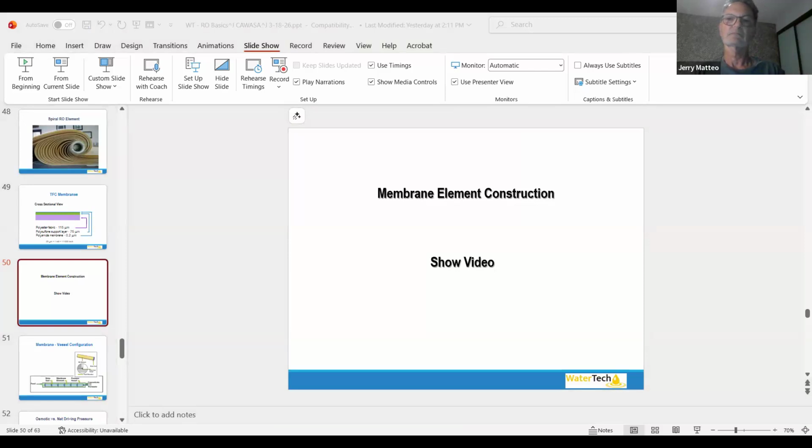We begin with a product water tube acting as the permeate collector. Sheets of the permeate carrier are welded to the product water tube. The number of sheets is preset depending on the specific element design. Membrane sheets are folded, barrier sides facing, and feed spacer material is inserted.